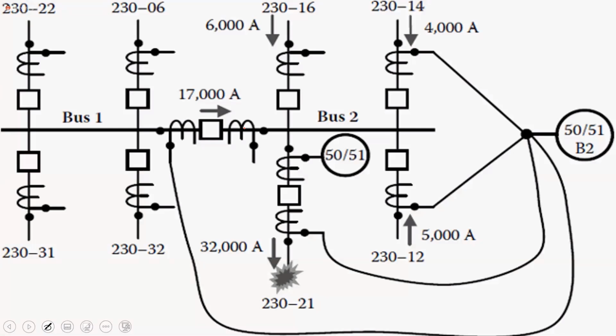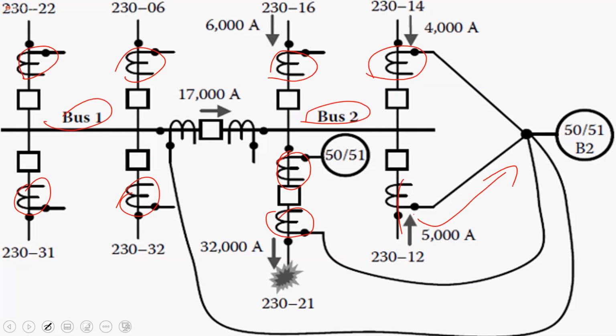All right, so here's my power system. I have my bus bar, and we talked about bus arrangements before. We just spoke about our CTs, right? And these would be our CTs. All right, so these represent the CTs, and what they are doing is just providing a replica of what's on the system. So if you have 5,000 amperes on this bus bar, then the CTs produce, based on the ratio, a certain output to that relay. Here you have 32 kiloamperes.